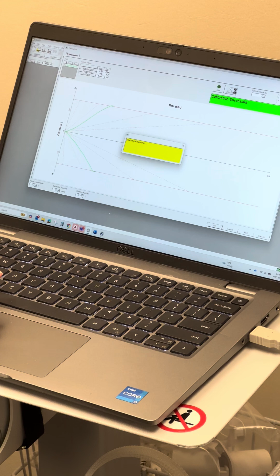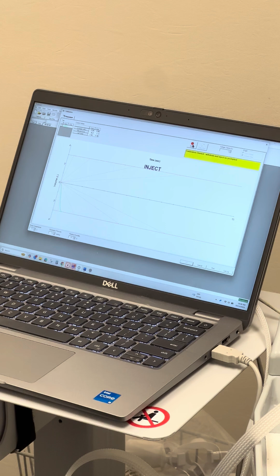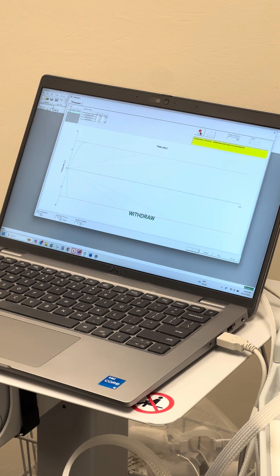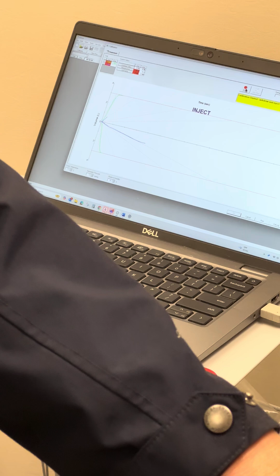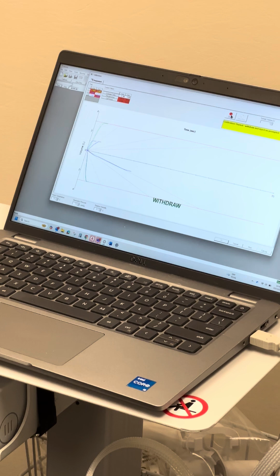The most common technical errors that happen during calibration usually occur with the slow and the fast stroke. And what happens with the fast is that I don't pause long enough before I inject, and it doesn't measure the full 3 liters. What happens with the slow is that I'm going so slow here, because I'm concentrating on the line, that it recognizes it as a stop. And here you can see I didn't measure 3 liters of volume. If I'm doing that fast, I don't pause long enough, again, I don't measure that 3 liters of volume.